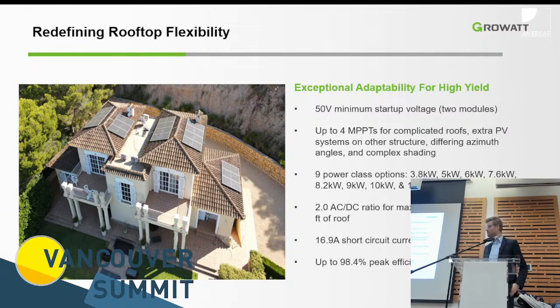The power classes are quite wide, starting at 3.8 kilowatts on the small scale, up to 11.4 on the larger units. The most attractive products here are specifically the 9 kilowatt, the 10 kilowatt, and the 11.4 kilowatt. The smaller ones are still interesting, but I will quickly talk about why the 9 kilowatt is so interesting. When you look at a solar-only installation in the typical household and typical electrical install the customer has, they either have a 100 amp service with a 125 amp bus bar rating of the panel, that's very common, or they have a 200 amp service with a 200 amp bus bar.